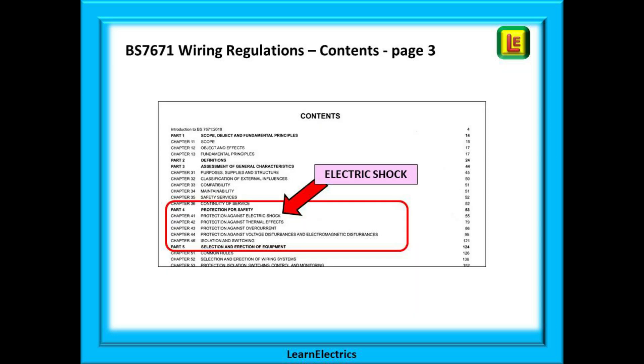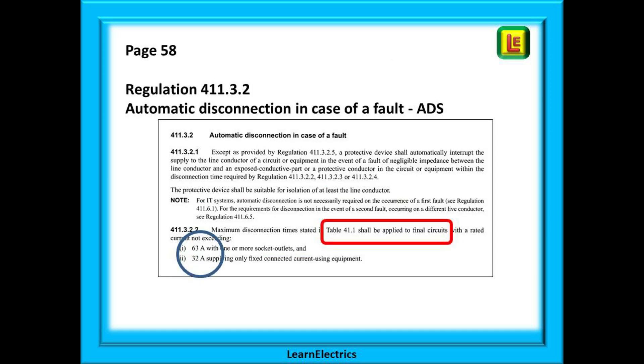If we recall from the previous video on using the contents pages, we will find on page 3 of the wiring regulations book the main contents page. Looking down the page, part 4 is all about protection for safety, and below this heading is chapter 41: protection against electric shock. This is where we will find information about ZS and disconnection times. Turning to chapter 41, we find regulation 411.3.2, titled automatic disconnection in case of a fault — shortened to ADS, automatic disconnection of supply. In other words, if a fault occurs the fuse or breaker will automatically disconnect the supply and make the circuit safe.